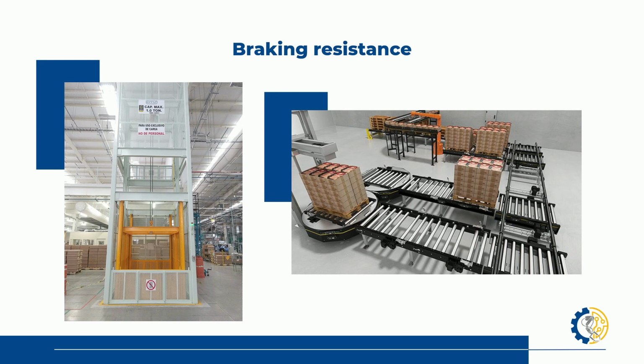Let's say, for example, that I wish to stop my motor and it has a very heavy load, in a short time lapse, but it's beaten by inertia. So what would happen here is we would need a brake resistance so that it can handle all that part that is regeneration, or anything that is exceeded.